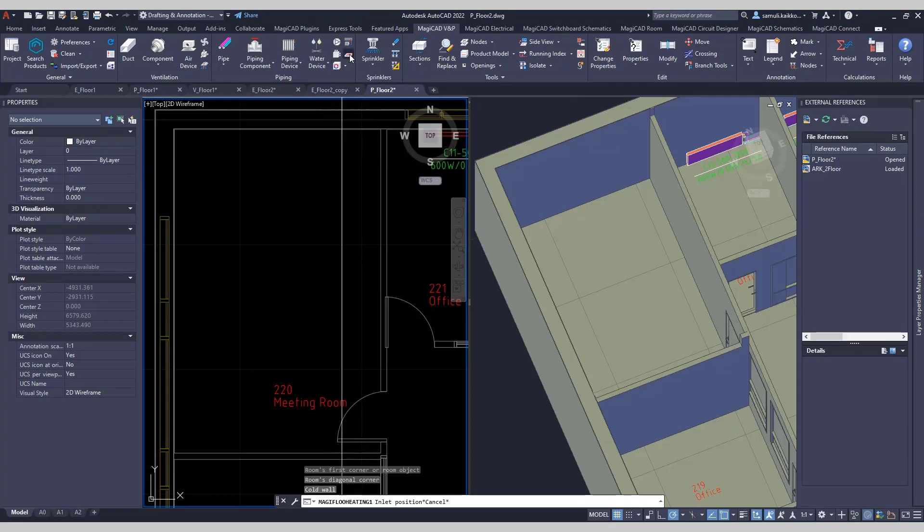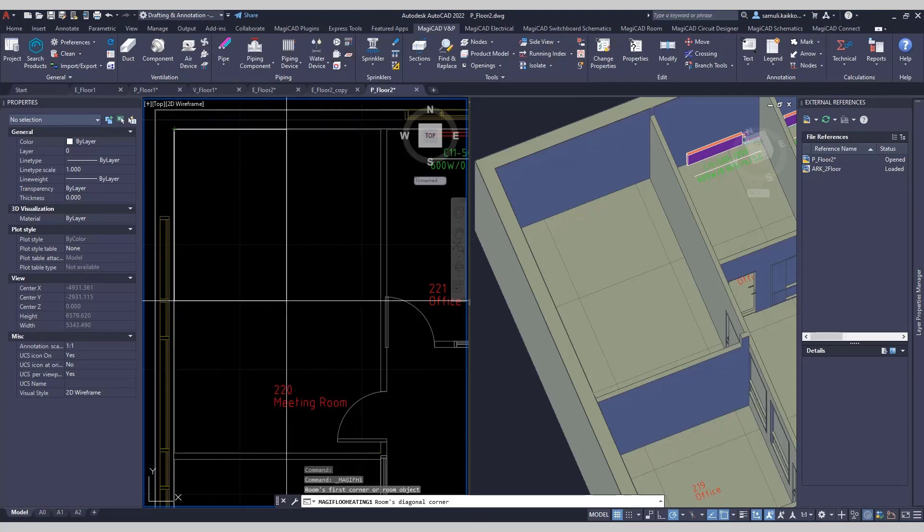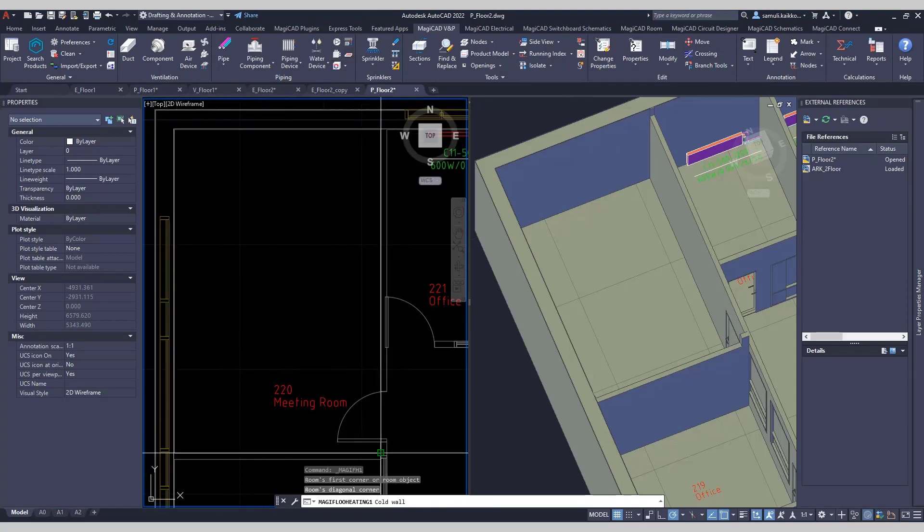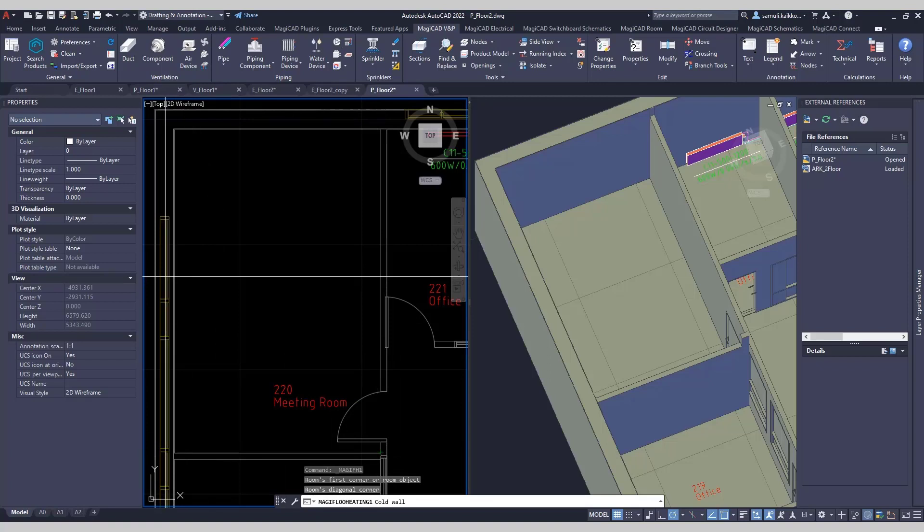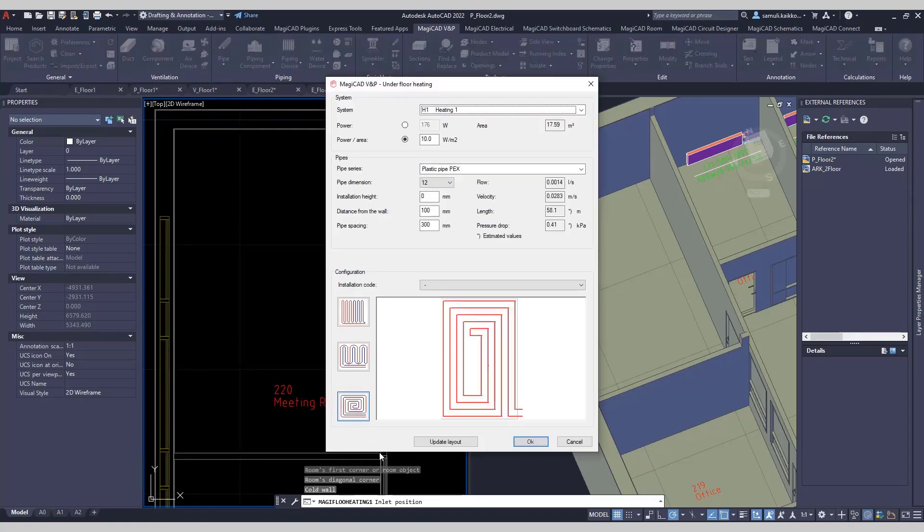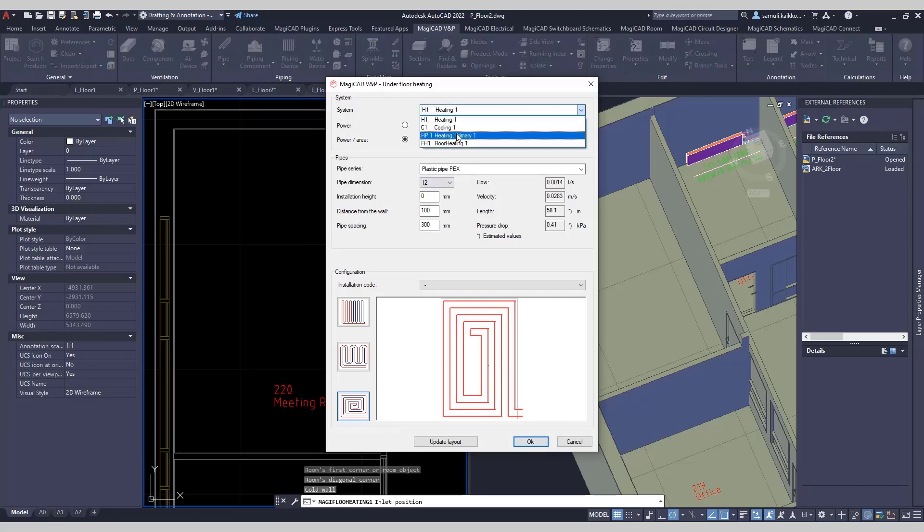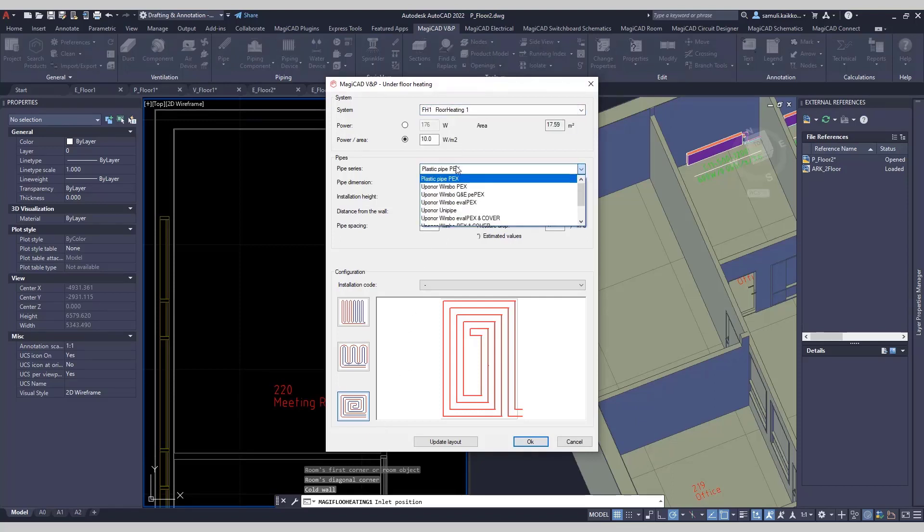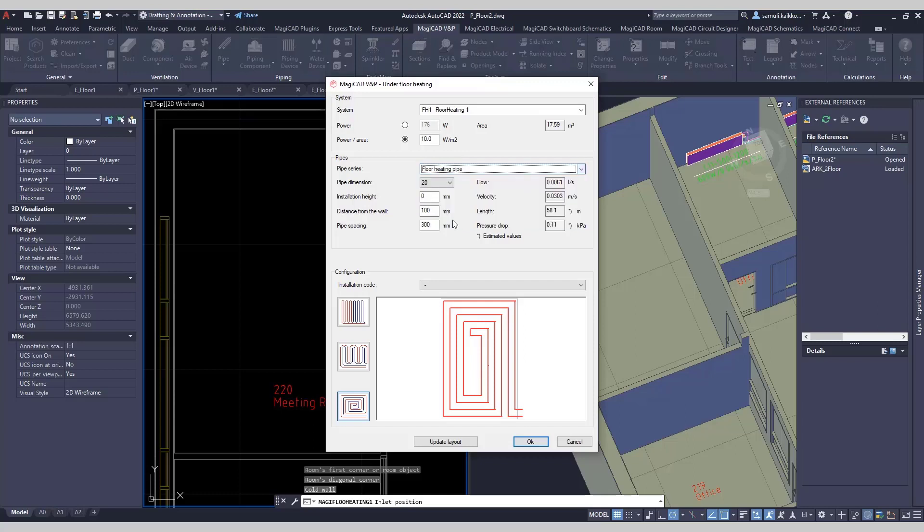There's an underfloor heating tool available now in MagiCAD for AutoCAD also. All you need to do is to draw a rectangular area for the heating, pick the cold wall side, and choose the place for inlet position. After this, MagiCAD automatically draws underfloor heating pipes.